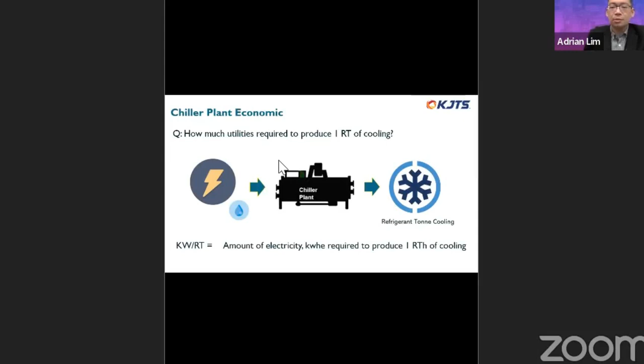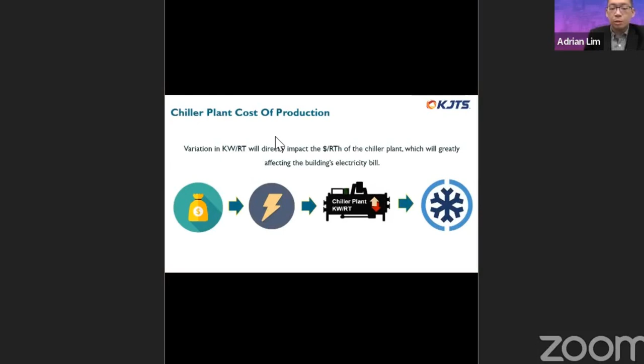The economics of the chiller plant encompass more than just COP, but the focus today will mostly be around COP. Logically, any variation in the kilowatt per RT will cause a direct impact to the COP, and we'll delve into this shortly.